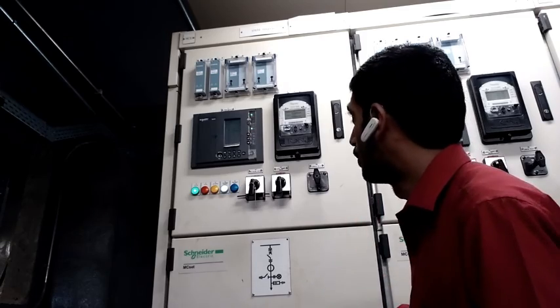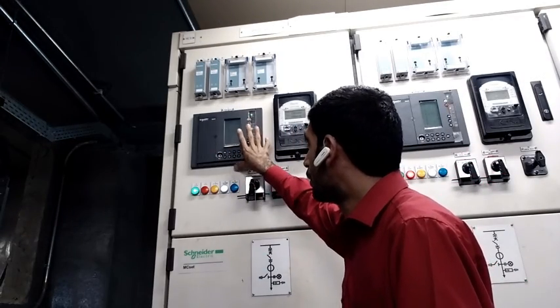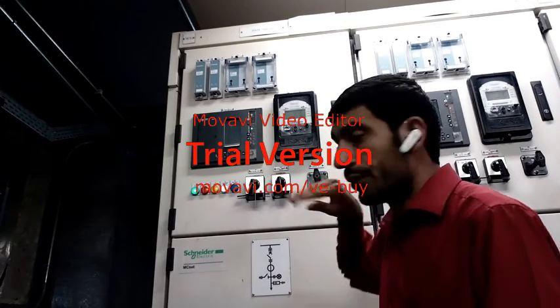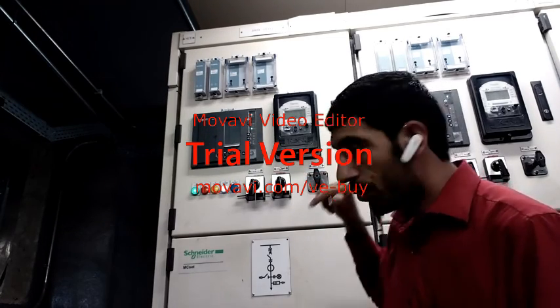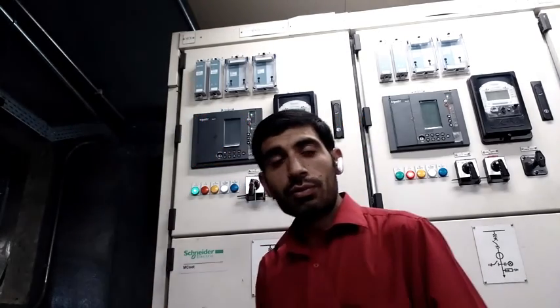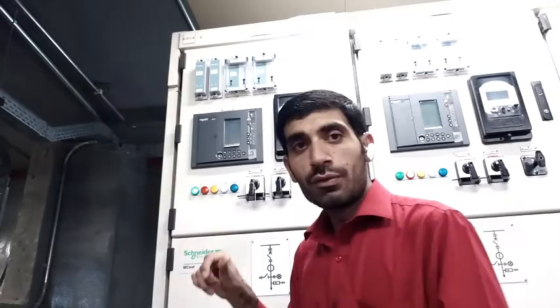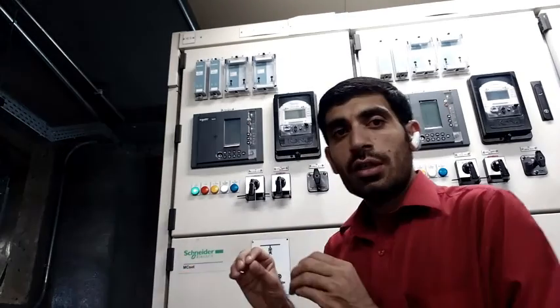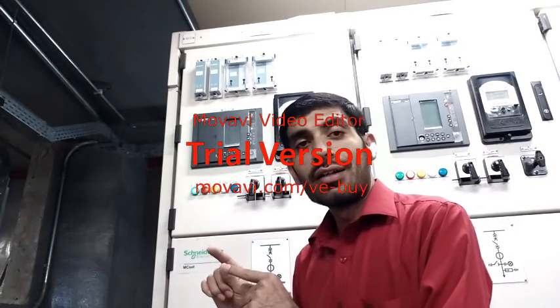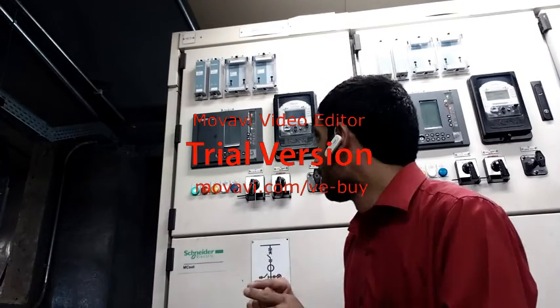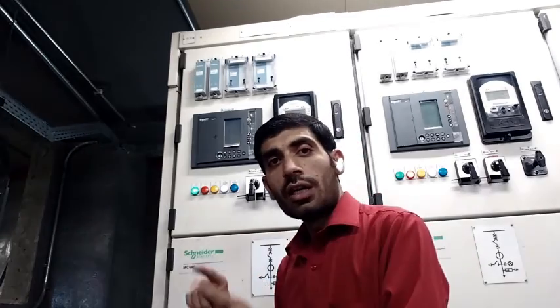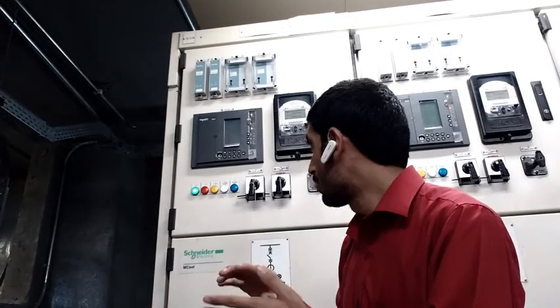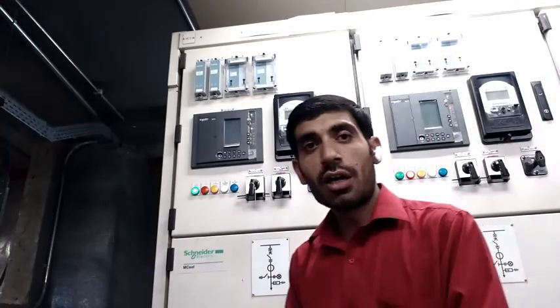we check pulse, and this protection relay we test through Freja. We also inject 3-phase voltage and current through Freja and increase the voltage up to 10% and check how much timing it takes. We select timing inside the relay, and then we check whether our relay is tripping within our selective timing, or how much error there is between the actual timing and rated timing. For over voltage, under voltage, and all faults, we tested all these through Freja, injecting the values and checking the time it takes for tripping, and checking the error.